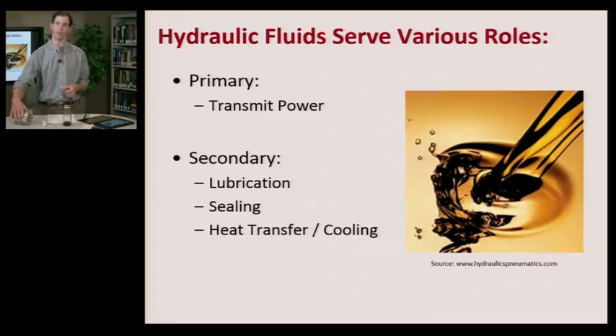Next is that it's also sealing, so again a piston to a cylinder or other locations where we have small clearances. Well the fluid provides enough viscosity that we are sealing those small gaps in our system and then also provides heat transfer because as we know we have inefficiencies in hydraulic systems and we need to transmit that heat out of our circuit some way. Well the fluid is what carries the heat out of our system.